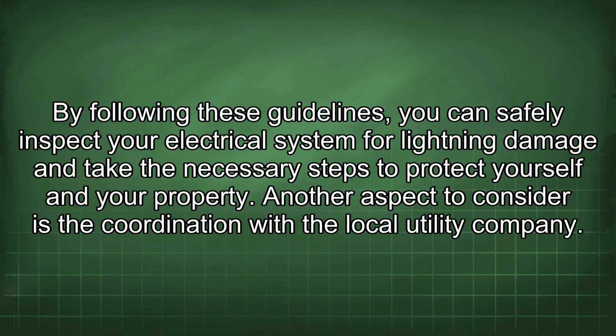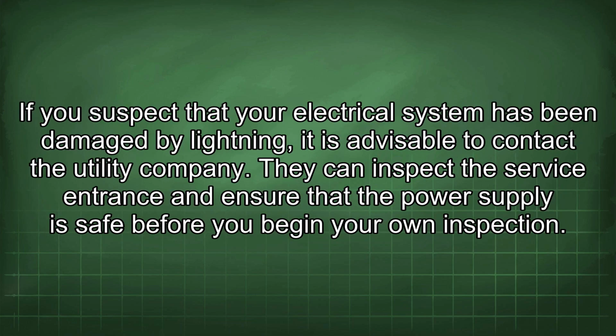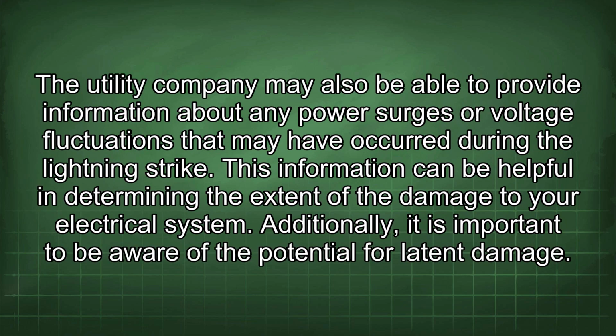Another aspect to consider is the coordination with the local utility company. If you suspect that your electrical system has been damaged by lightning, it is advisable to contact the utility company. They can inspect the service entrance and ensure that the power supply is safe before you begin your own inspection. The utility company may also be able to provide information about any power surges or voltage fluctuations that may have occurred during the lightning strike. This information can be helpful in determining the extent of the damage to your electrical system.